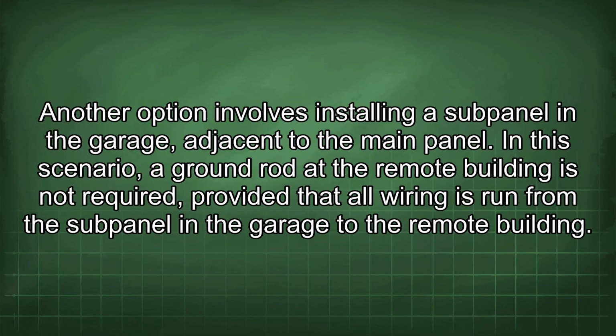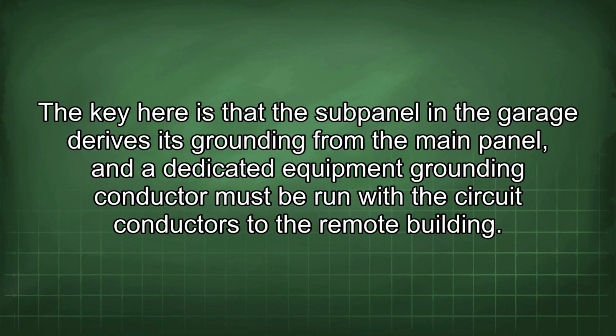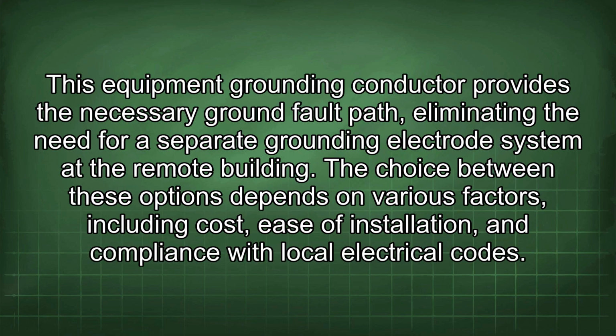Another option involves installing a subpanel in the garage adjacent to the main panel. In this scenario, a ground rod at the remote building is not required, provided that all wiring is run from the subpanel in the garage to the remote building. The key here is that the subpanel in the garage derives its grounding from the main panel, and a dedicated equipment grounding conductor must be run with the circuit conductors to the remote building.